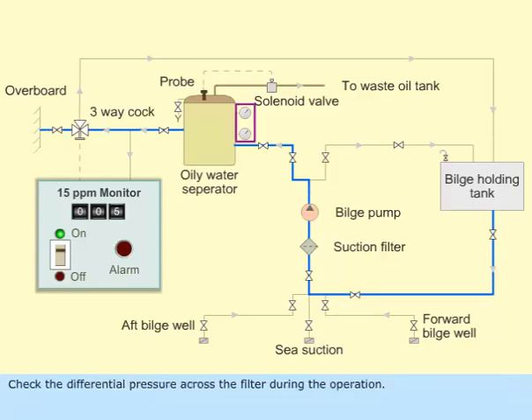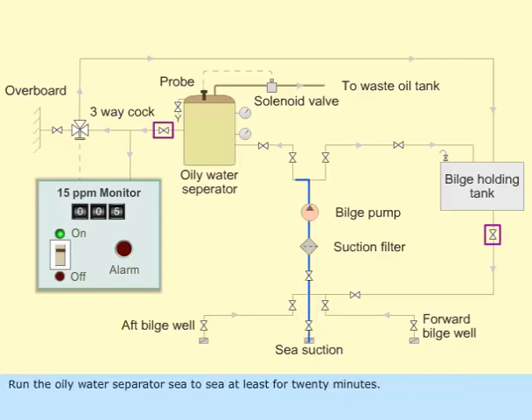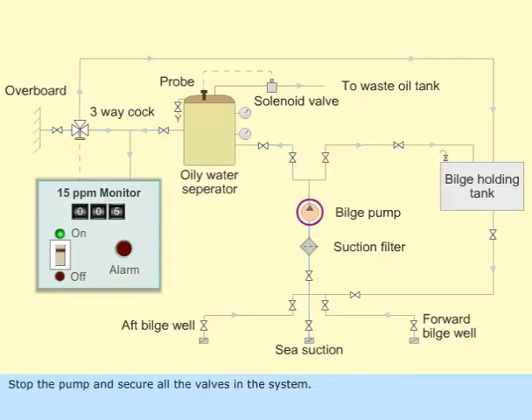Check the differential pressure across the filter during operation. On completion, open the sea suction valve and close the bilge holding tank valve. Run the oily water separator sea to sea for at least 20 minutes. Stop the pump and secure all the valves in the system.